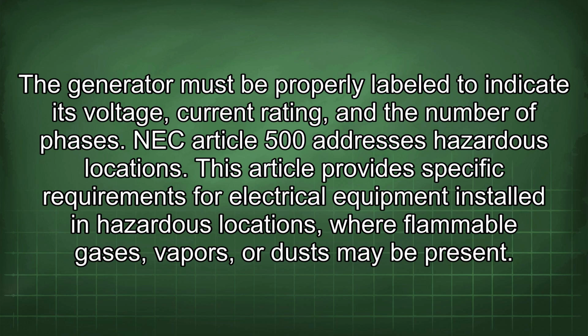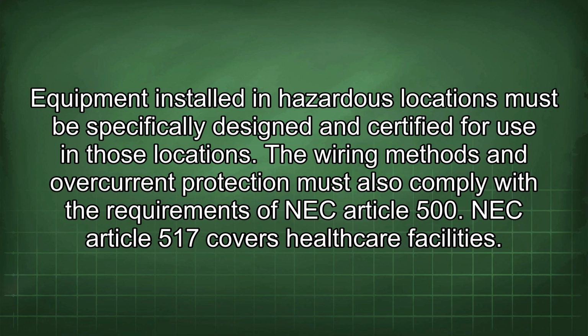NEC Article 500 addresses hazardous locations. This article provides specific requirements for electrical equipment installed in hazardous locations, where flammable gases, vapors, or dust may be present. Equipment installed in hazardous locations must be specifically designed and certified for use in those locations. The wiring methods and overcurrent protection must also comply with the requirements of NEC Article 500.